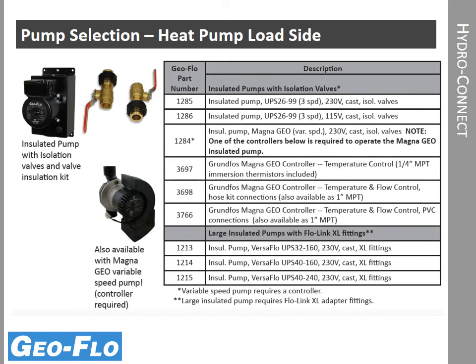So then let's look at pump selection. I mentioned it's a modular system. So we have the buffer tank, we have the controls. Those can be purchased together or separately. And then we need a pump for the heat pump load side, the water-to-water or combo unit, to pump from the heat pump over to the buffer tank. In this case, we have a number of different choices. In the picture here on the left-hand side, you can see a typical insulated pump. That's a single-speed pump. This one actually 3-speed, but constant speed. With isolation valves, we can go with a variable speed pump, larger pumps. So there's a variety of different pumps from the load side over to the buffer tank.